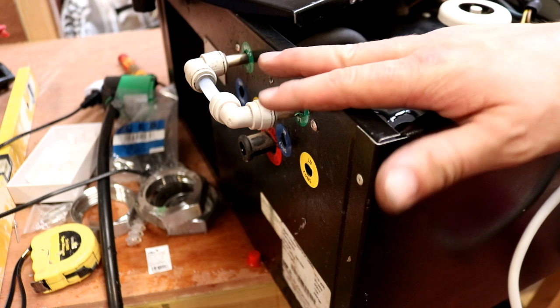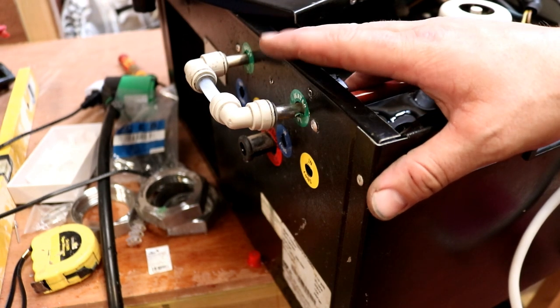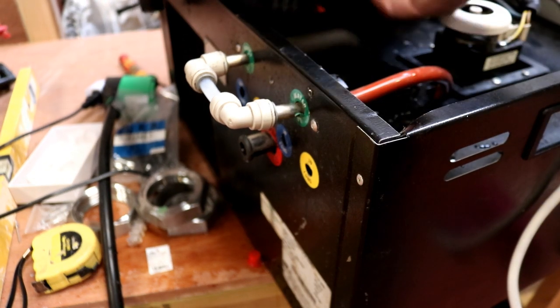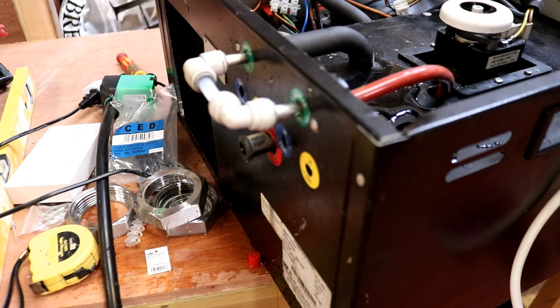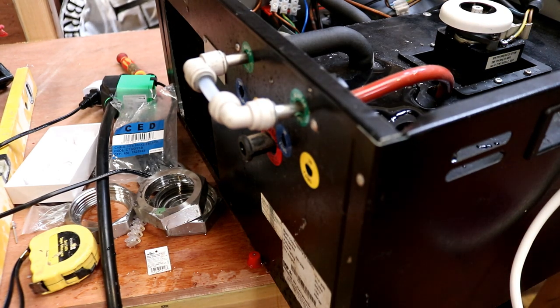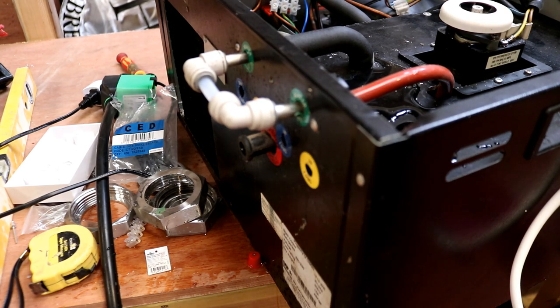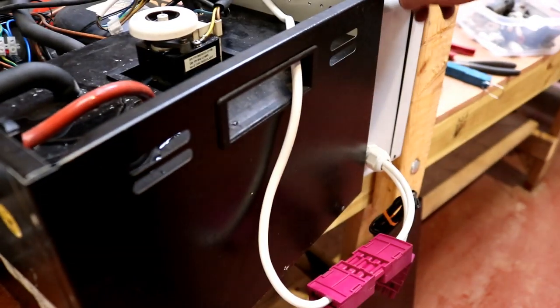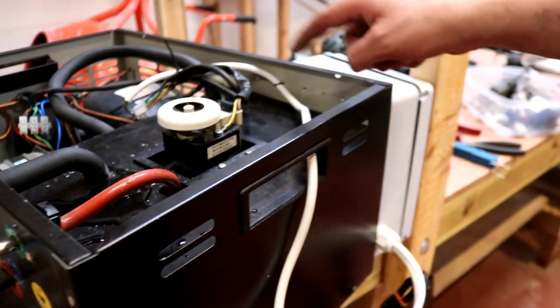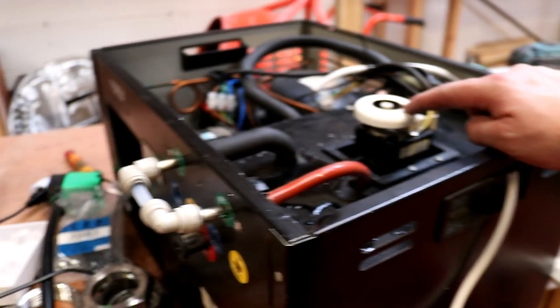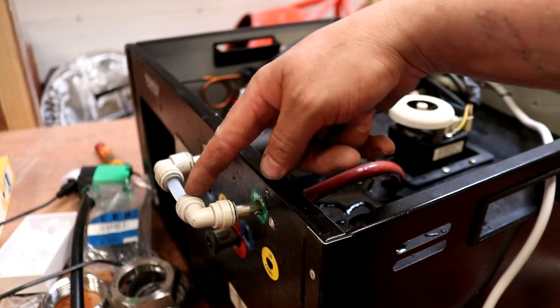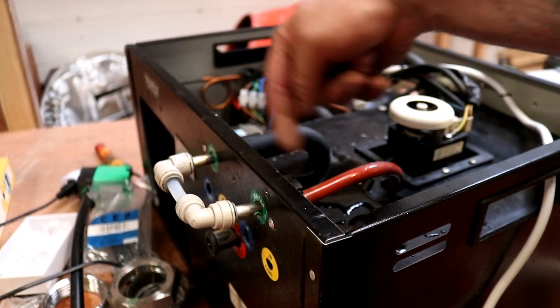Because it's got a 5 minute delay on this machine that you saw me set earlier on, we'll time that 5 minute delay out, and then we'll also watch what is happening with the control unit, because this is what should kick on the recirc pump. And then in order to see if it's actually working, I've just set up this little - this is the flow.